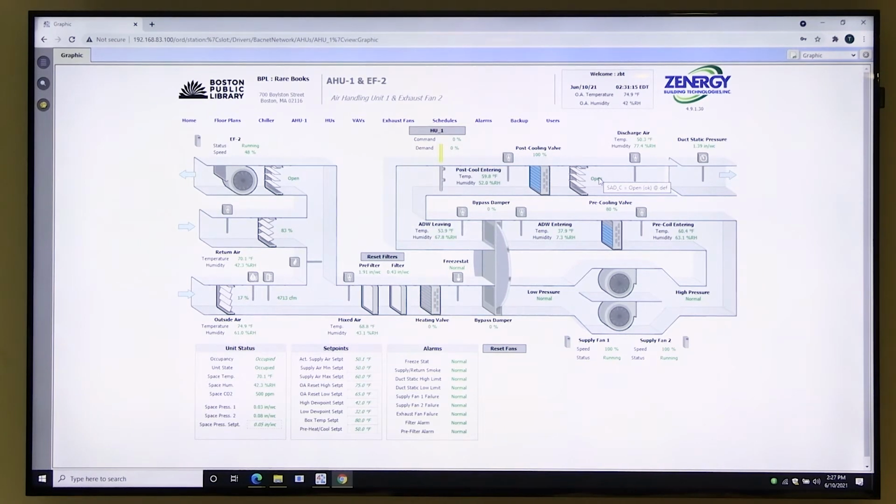I'm surprised they put the humidification before the post-cooling valve. Yeah, that's a good question. I can double check to make sure that's the actual location. That should be flipped, or you're just going to pull that humidity back out. You typically wouldn't be humidifying and cooling at the same time, so I'm not sure it would matter, but I'll double check that orientation just to make sure that's how it is, and get back to you on the walkthrough.